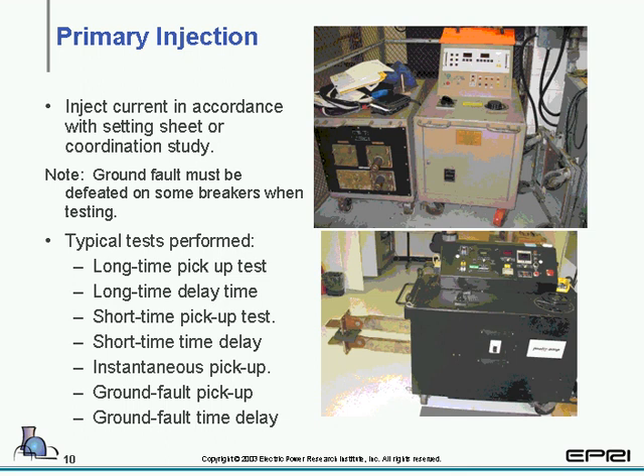If you take a look at the long time, there are actually 2 tests performed here. The very first one is pickup. Pickup has nothing to do with time. When you're performing long time, short time, and ground fault, you must keep in mind that you do pickup testing and then time delay. There's no time delay associated with instantaneous, which is self-explanatory because instantaneous is as fast as the breaker can come offline. Typically, long time is in seconds, short time is in tenths of seconds, and instantaneous is within hundredths of seconds. Ground fault tends to mimic short time, except that the current values are much lower.